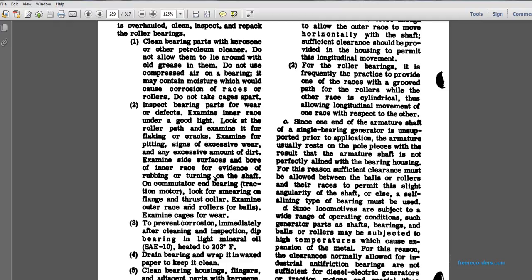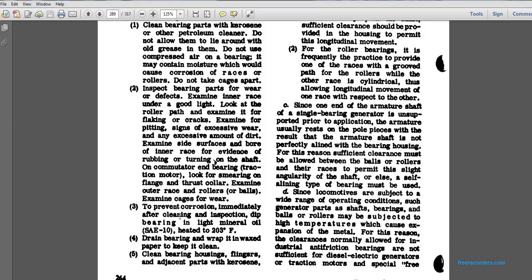Examine the inner race under good light. Look at the roller path. Examine it for flaking or cracks. Examine for pitting and signs of excessive wear, and any excessive amounts of dirt. Examine the side surfaces and bore of the inner race for evidence of rubbing or turning on the shaft. On the commutator end bearing of the traction motor, look for smearing on the flange or thrust collar. Examine the outer race, the rollers or balls. Examine the cage for wear.